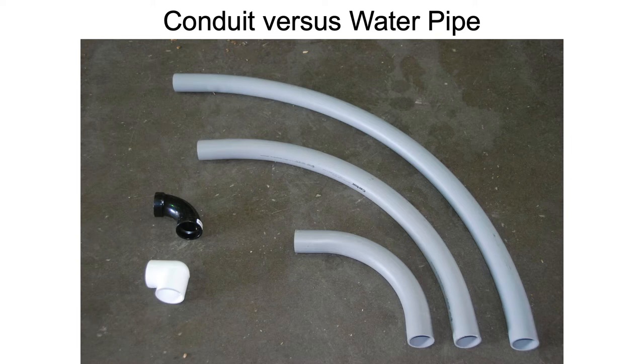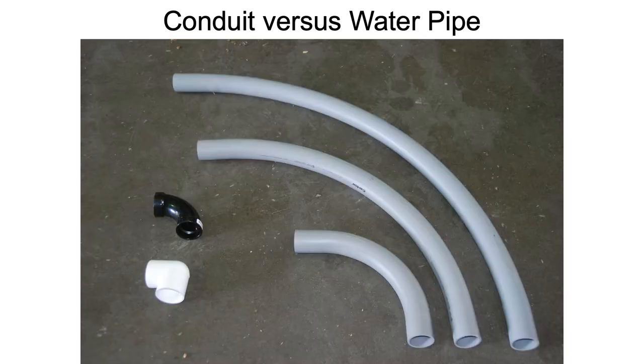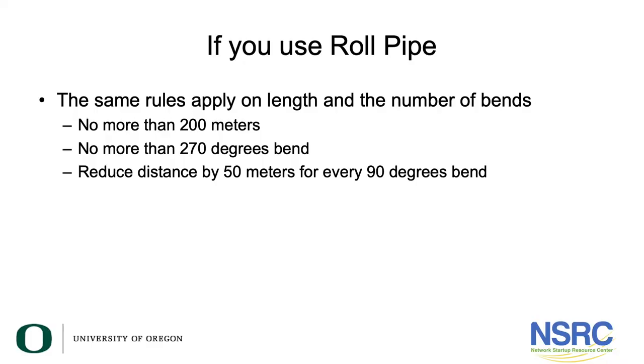The three on the right-hand side with large circumference are all appropriate for fiber optic cable. All of these pipes shown are 50-millimeter pipes. The gray pipe on the very top-right will be much easier to pull into than the gray pipe on the bottom, simply because of the bend radius. If you're using roll pipe, think about bend radius too — when making a 90-degree turn, do it in a gradual fashion so it's easier to pull fiber through.